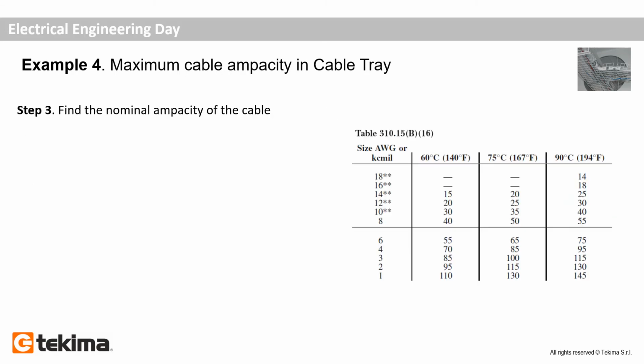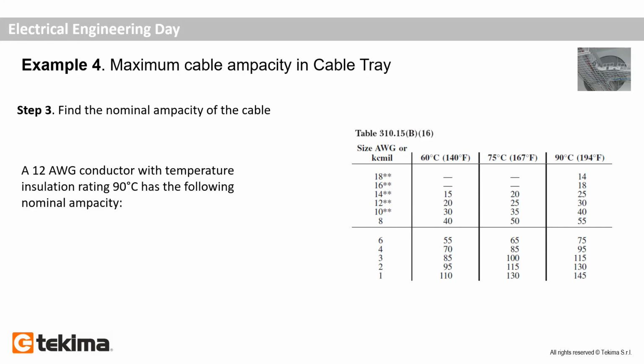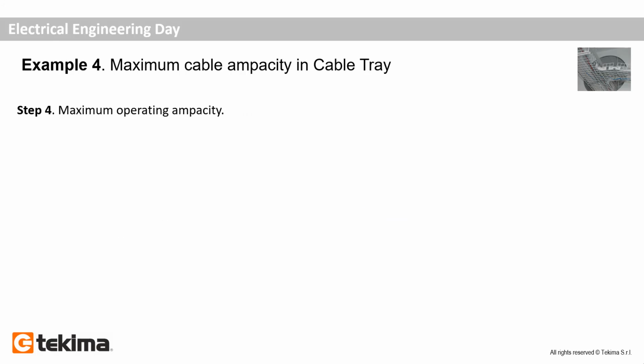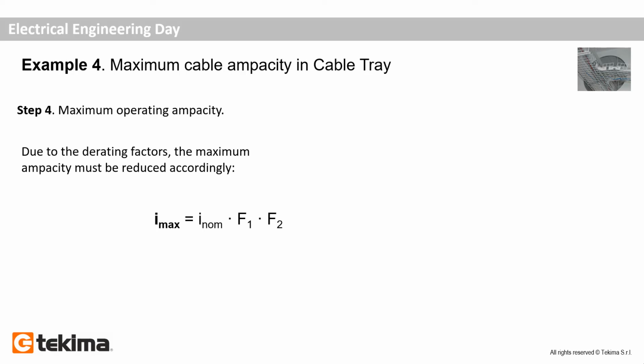Step 3. Find the nominal ampacity of the cable. Again, using the table contained in the standard, we can find that for a 12 AWG cable with a 90-degree temperature rating, the nominal ampacity will be 30 amperes. So we can calculate the maximum operating ampacity of the cables installed in the cable tray, which is the nominal ampacity multiplied by the rating factors. 30 amperes multiplied by 1 multiplied by 0.8, which is the rating factor due to the conductors grouping. In this case, we have 24 amperes.